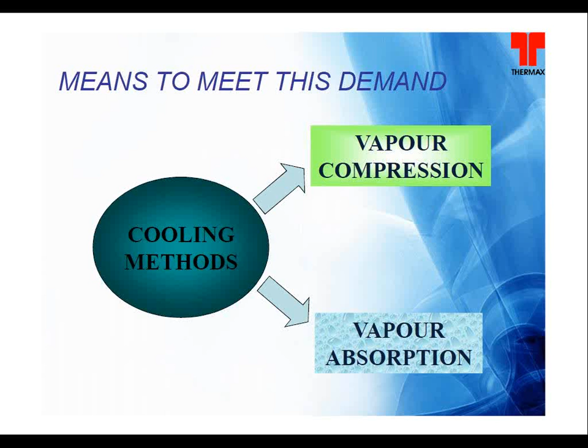As mentioned in my introduction itself, I represent the cooling division of Thermax for Northern India. There are actually two methods by which we can generate chilled water or a brine which is below 0 degree. One is the vapor compression cycle, which is a traditional cycle used almost everywhere in the globe, and the other cycle is the vapor absorption machine. The vapor absorption cycle basically works on the heat principle, whereas the compression cycle works on the high grade energy, which is nothing but the electricity.